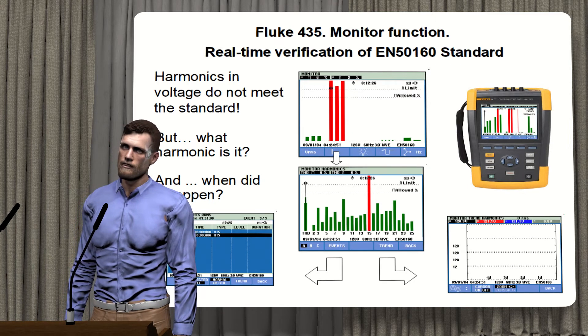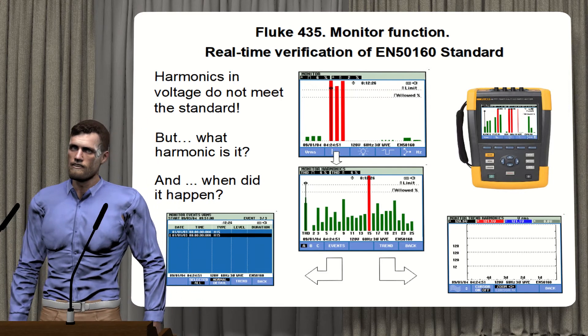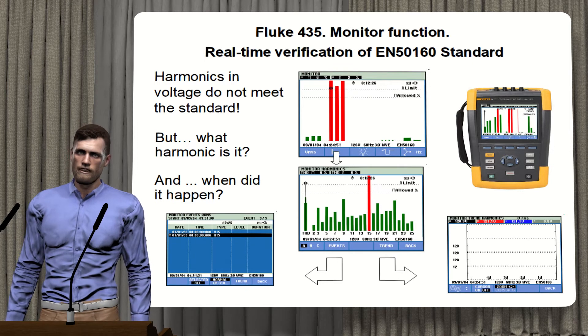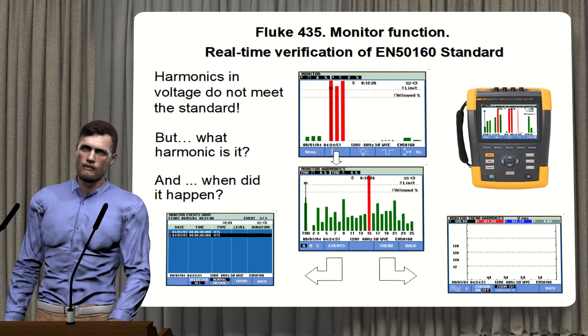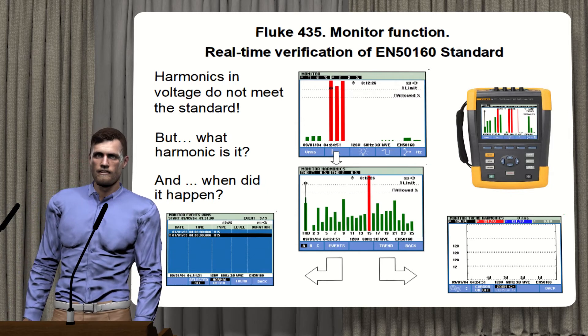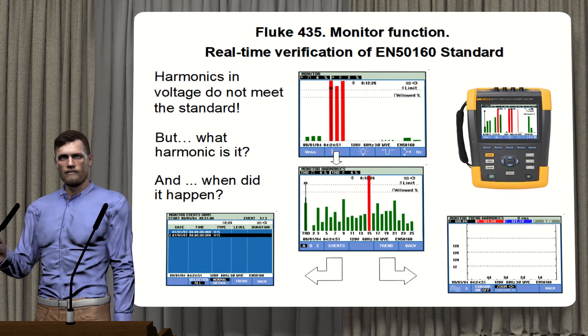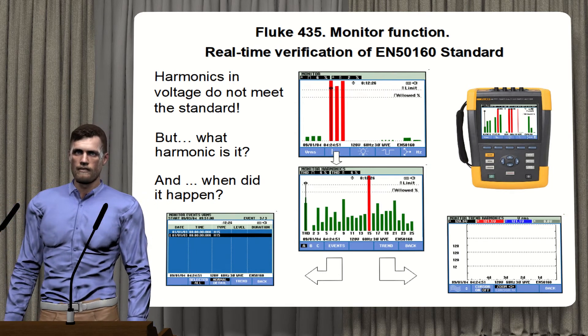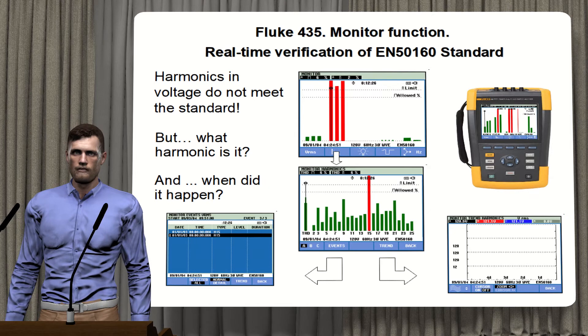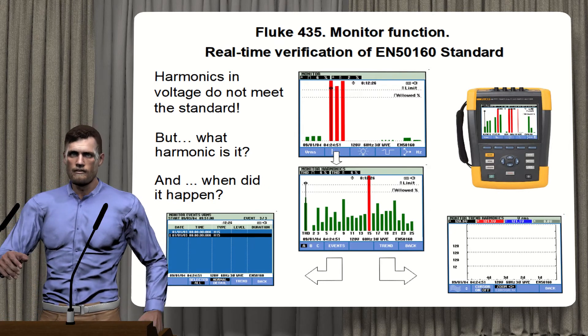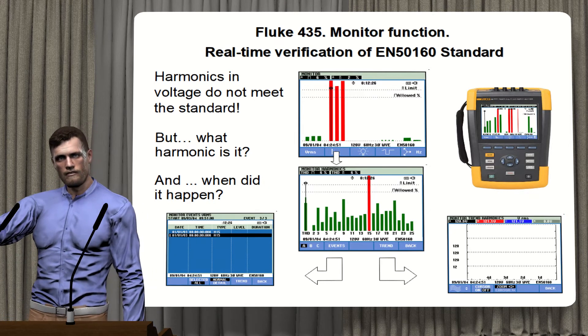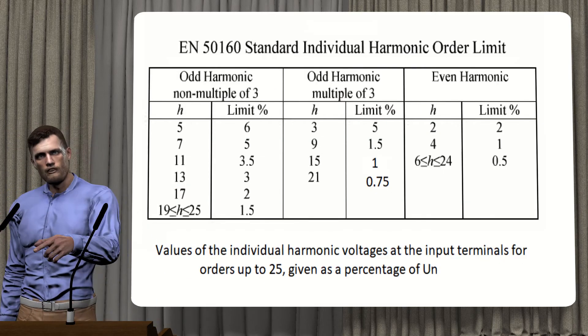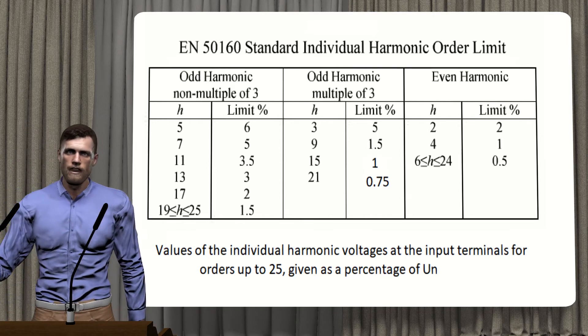The Fluke 435, 1738 and 1748 have the EN50160 standard memorized, thus allowing a simple automatic verification of the measurements obtained according to this standard. This can be done through the monitor function that these analyzers incorporate, allowing a graphical view of compliance with the standard and generating a report via software. Thanks to this function, we can not only determine if the THD value is acceptable, but also the value of each voltage harmonic, since these analyzers also have memorized the limit established by the EN50160 standard for each voltage harmonic.